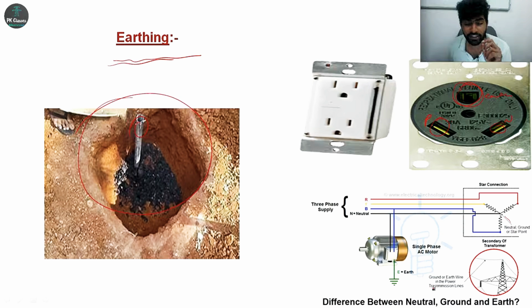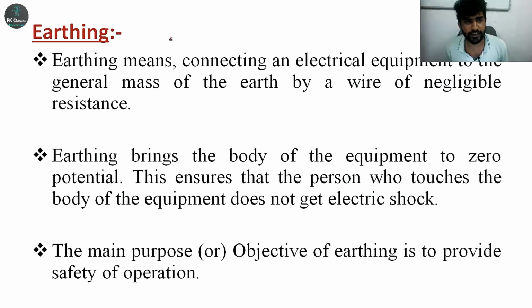We'll see the difference between neutral, ground and earth. See here, earthing is connected to the body of the equipment. If you touch the body of the equipment, you will not get a shock, right? Neutral and ground provide a continuous path for the electricity, right? Earthing and grounding have about 90% similarity. But earthing has zero potential, while grounding has no zero potential. And in earthing, resistivity is less, but in grounding resistivity is not less. This is the earth wire in the transmission lines; the center one is the earth wire. We'll discuss earthing and types of earthing in detail. Earthing is mainly for human safety as well as equipment safety, right?